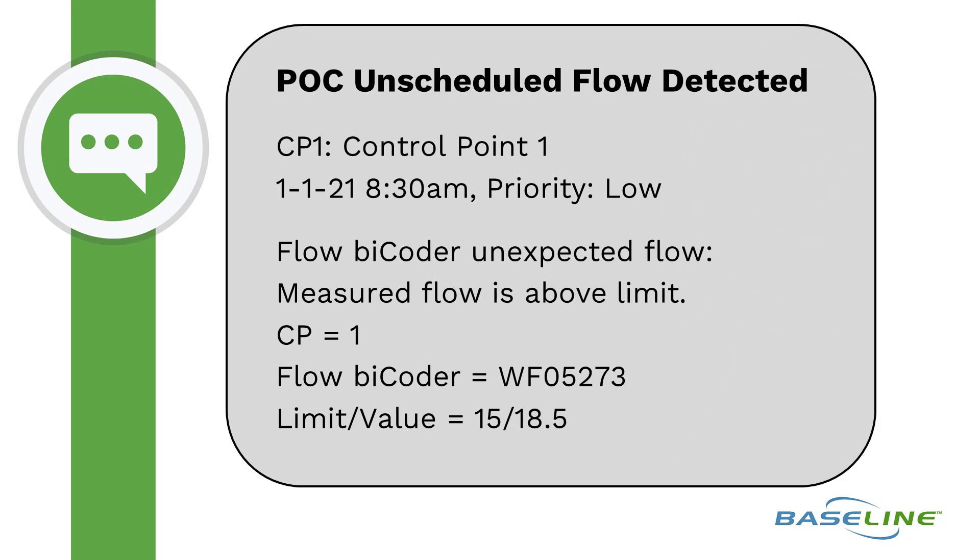Looking at the message again, we see control point 1 saw the unscheduled flow, which was measured by flow biCoder WF 05273. Notice that the limit and actual values are measured in gallons per minute. The controller expected up to 15 gpm of unscheduled flow, when in fact it saw 18.5 gpm.